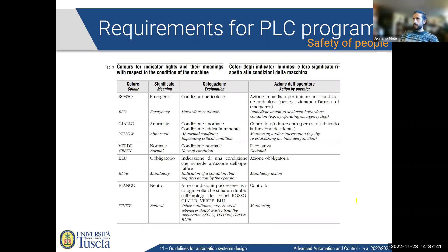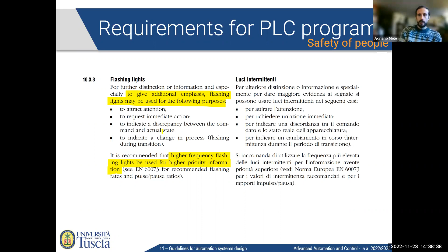In addition, you can have flashing lights used for different purposes: to attract attention, to request an immediate action, to indicate a discrepancy between the command and the actual state, to indicate a change in progress, and so on. In general it's recommended that higher frequency is used for higher priority information. This shows how specific these regulations can get - even the color of things or the frequency of a flashing light can be subject to a specific indication or prescription you should implement.